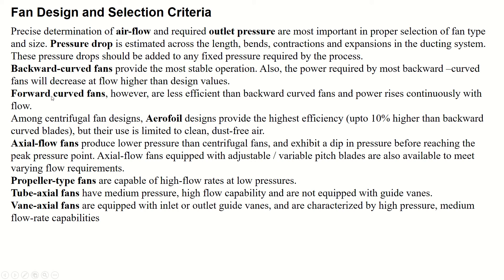Forward curved fans are less efficient than backward curved fans, and their power rises continuously with flow. Among centrifugal fans, airfoil designs provide the highest efficiency — up to 10% higher than backward curved blades — but their use is limited to clean, dust-free air.